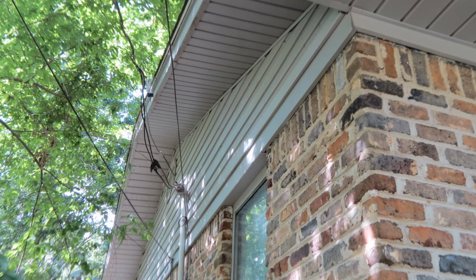What you're looking at in this photograph is a service drop that is missing the drip loop or drip leg, where the wire would come down and make a loop down below before entering the weatherhead. So what's happening is, every time it rains, water runs the length of these wires all the way into the weatherhead, and it can drip down this service mast into the electrical panel down below.